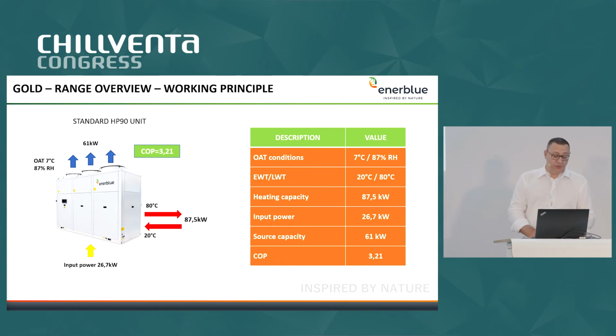Concerning the working principle, here we have the standard unit, air-to-water. So for sure, it is an electric heat pump, so there is the input power from the network. This unit, in this case, is sized to produce 80 degrees leaving water temperature with 20 degrees at the inlet. And of course, the source fluid in this case is air. With this condition, we are producing more or less 88 kilowatts in heating, and from the source, we are using 61 kilowatts from outdoor air. With this condition, we can have a COP of 3.21 with 80 degree leaving water temperature.